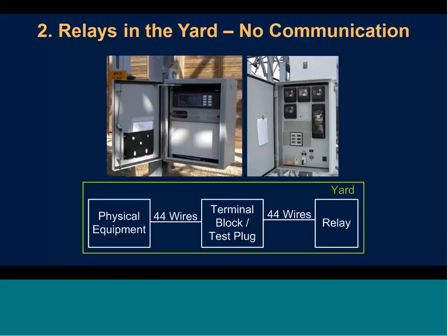So one way to reduce the amount of wiring is essentially to distribute that control house. One possible way is to put the relays out into the yard and have each relay communicating and protecting locally. In this case, we can cut out all of the wiring from the yard to the control house. This is similar to an approach we'll talk about later, with one key difference that we'll touch on when we get to that.